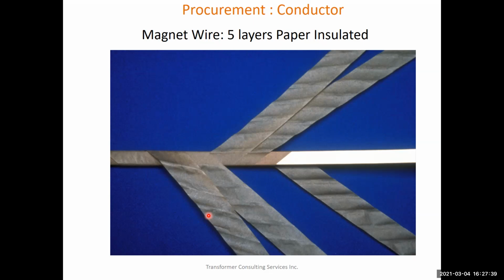3 years ago, when we bought the second transformer from the same manufacturer, the manufacturer moved from 50 mil to 45 mil. Now, last year, the beginning of last year, when we were buying the third transformer from the same manufacturer, the manufacturer gave us 40 mil. Just see, within 5 years, the manufacturer moved from 50 mil to 40 mil. That means reduced 10 mils into the insulation because the manufacturer became more aggressive into design. But at the same time, the factory quality has not been improved. So that means the transformer is being stressed over here in terms of quality.